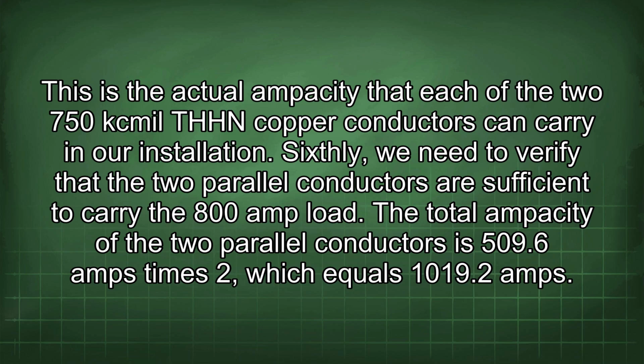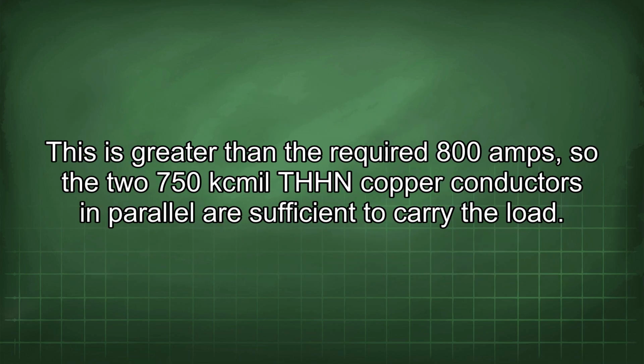Sixthly, we need to verify that the 2 parallel conductors are sufficient to carry the 800 amp load. The total ampacity of the 2 parallel conductors is 509.6 amps times 2, which equals 1019.2 amps. This is greater than the required 800 amps, so the two 750 kcmil THHN copper conductors in parallel are sufficient to carry the load.